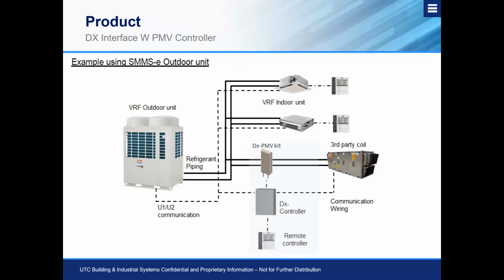So what we're essentially using is the PMV kit, or this refrigerant management kit, paired with some form of controller, so we can operate off of a 0 to 10 volt signal, or more commonly operate off of the return air. We need both for it to work in unison, plus the custom third-party coil that's developed depending on the capacity we need to fit into the air handler that we're trying to remedy. So essentially, we're converting what wasn't heat recovery into heat recovery.